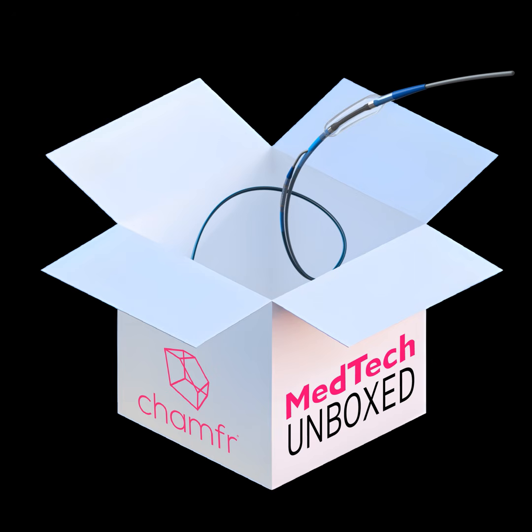Number one, with PTFE you can achieve a very, very thin wall. I'm talking about under 0.0005 or under half a thousandth. It's a paste extrudable material, so it's much easier to hold thinner walls and tight tolerance. Because of that, in many applications such as microcatheters, neurovascular, and catheter-related applications, they really require thin wall, because every half a thou or every quarter thou really matters a lot. In those cases, PTFE is one of the only polymers that can achieve that.